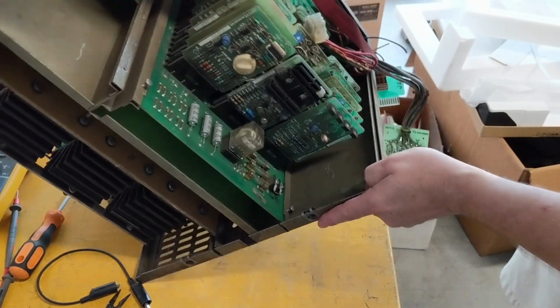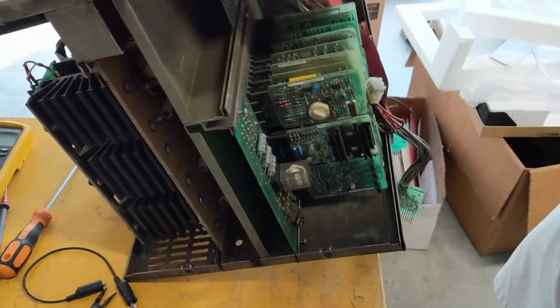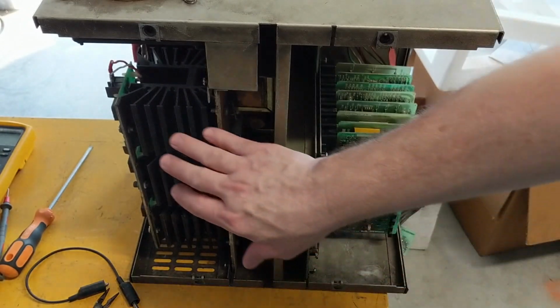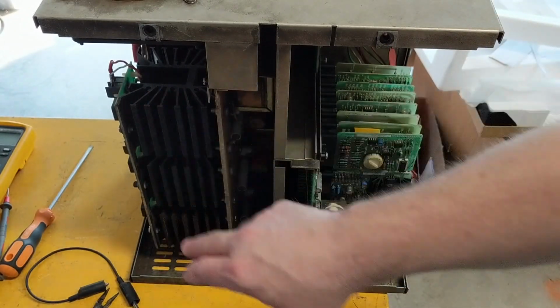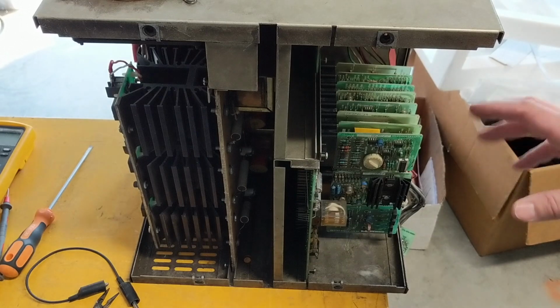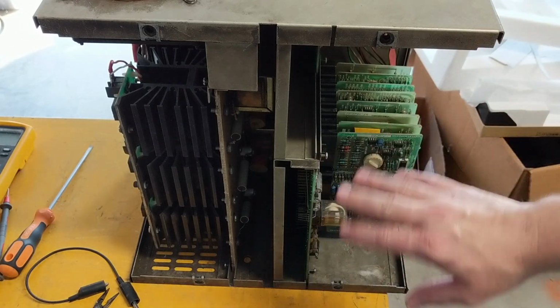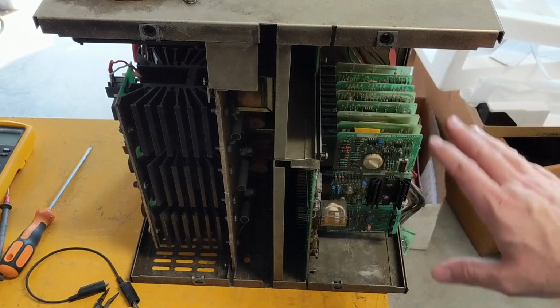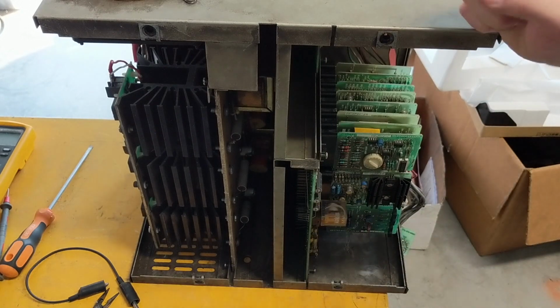As well as check, especially this drive that was having issues with the power block, the SCR is firing on the oscilloscope, just didn't look right on the power block on this drive running. So with this being a 20 horsepower drive, after I get some of my basic checks done, the next step will be to load test it, which I can't do here.